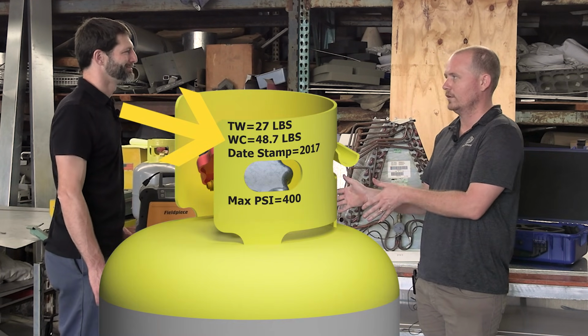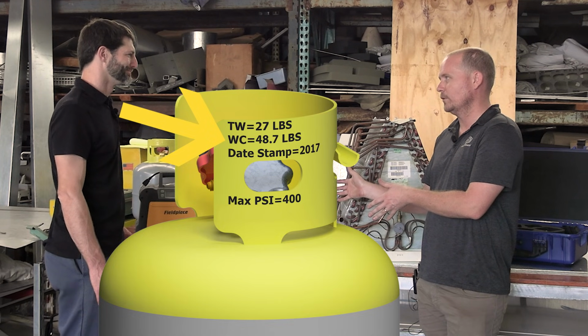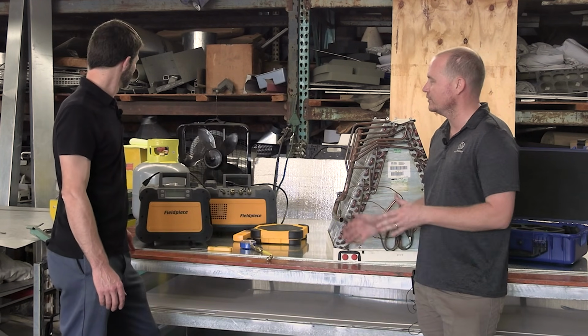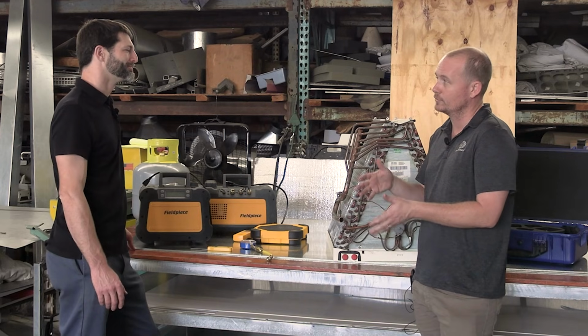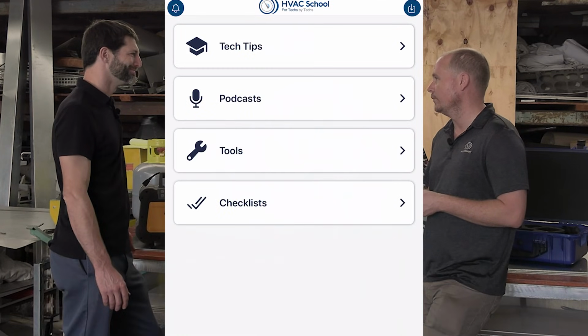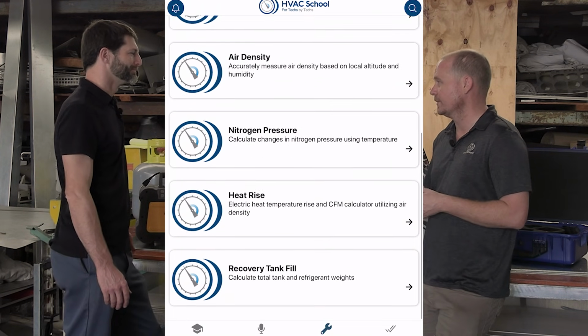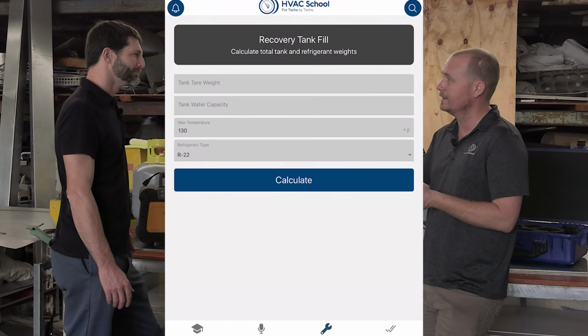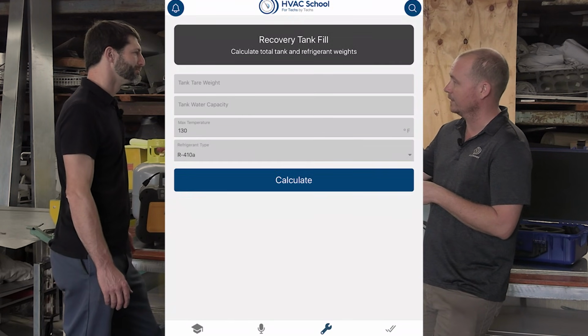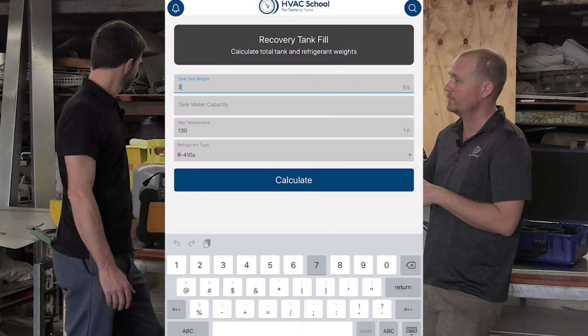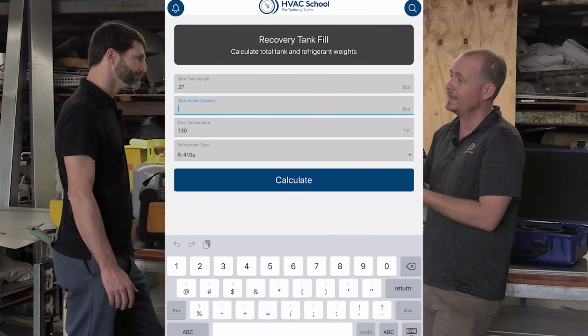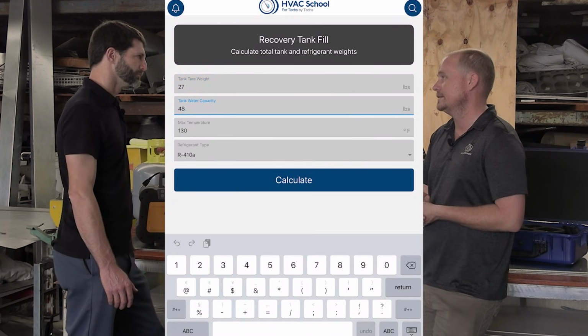Right. The thing that throws a lot of people off and really makes this difficult is that the tank has a WC printed on it, which is water capacity, but of course we're not putting water inside the tank. So you have to do some math in order to figure out how much refrigerant you can put in the tank, and you can go to my app, the HVAC School app. It's free, and there's a calculator in there that you can plug in different refrigerants. You can calculate based on the tare weight and the water capacity what the fill should be in the tank, and then what your maximum total tank weight should be.